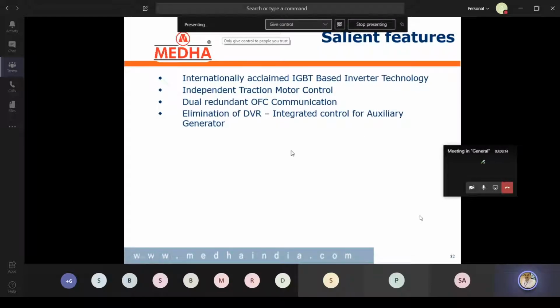Elimination of DVR, integrated control for the auxiliary generator. DVR is the digital voltage regulator module. In EMD, a separate DVR module is there, which controls only the auxiliary generator. But in our case, we have eliminated the DVR so that the failures related to the DVR can be eliminated. And further, through the common control unit, using an inbuilt feature, the auxiliary generator will also be controlled.